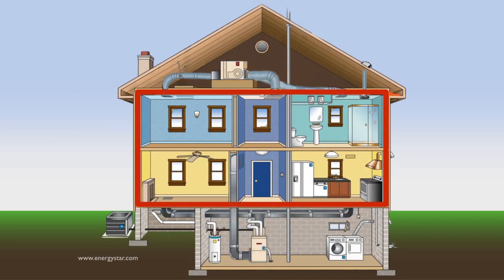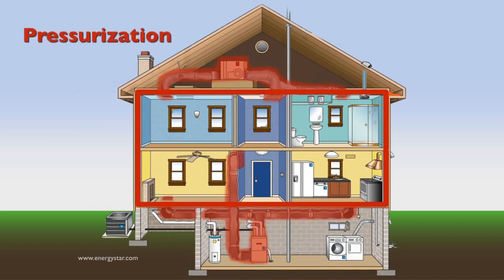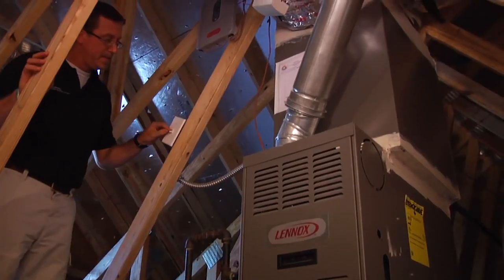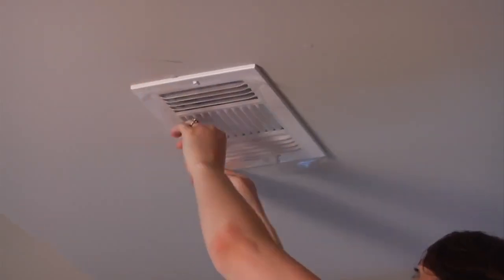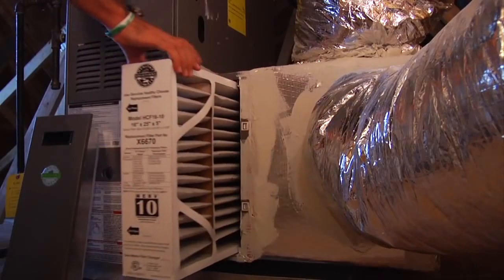In this video, we will be demonstrating the pressurization test. This is the most common way to measure duct leakage as it requires less equipment. It is important to set up the house properly to make sure the test is accurate. To set up the home, turn off all fans in the home, including the air handler.